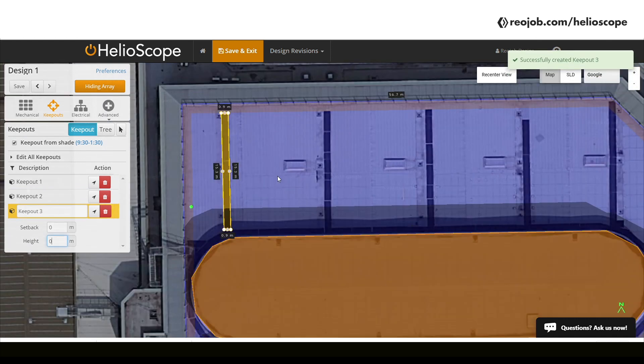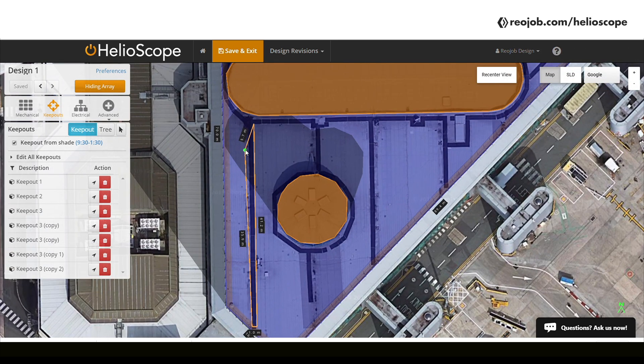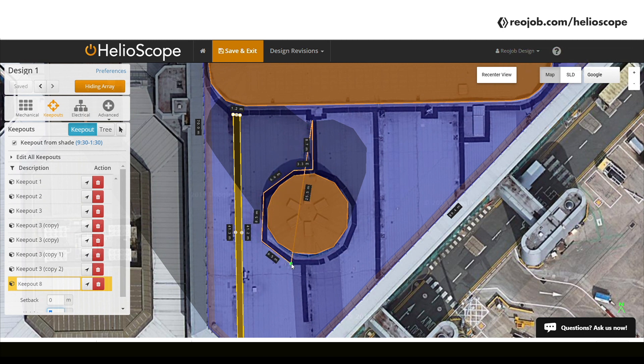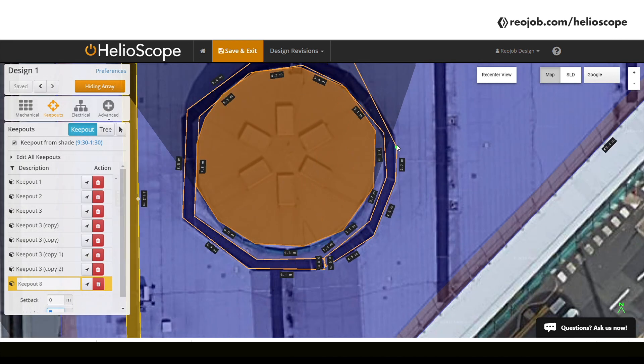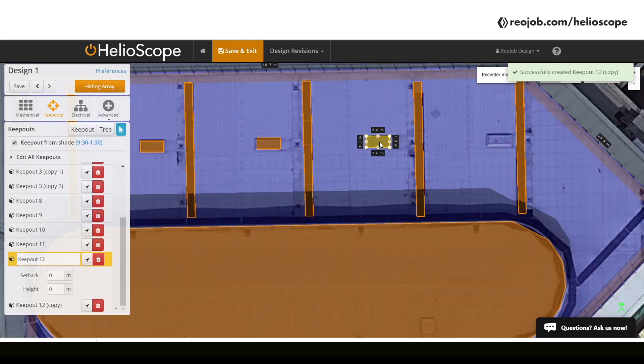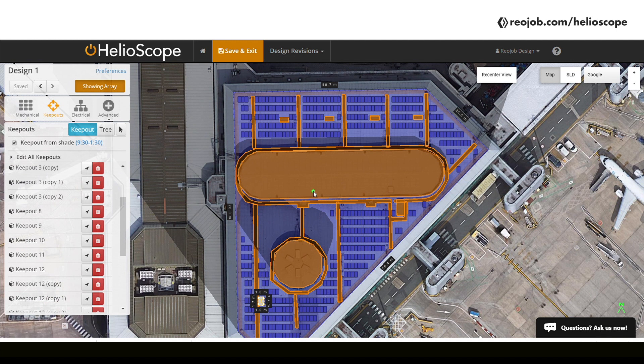Sometimes you may have similar obstructions, and instead of tracing them individually, you can simply duplicate them. You can always further tune your tracing to ensure accurate designs. You may have noticed that after adding these obstructions, some panels on this rooftop may have been deleted. This happens because the software calculates the shadow profile of the obstruction and removes any panels that are partially or fully shaded. Understanding the importance of shading losses is essential to improve your plant's energy generation.